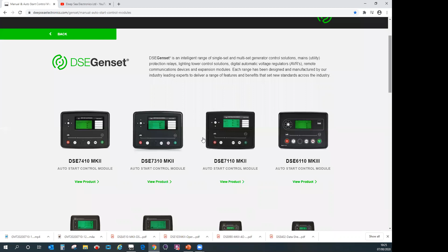So this one here, the auto start control, if we take a common module, which is a good example, the 7310. 7310 means that it's a standalone generator controller, and basically it will start the generator and open and close a breaker. Okay, and it will do that automatically. When it's in auto mode, if someone wires an input to the controller and flicks a switch, the generator will start automatically, or it might be on a schedule, so it will start automatically every couple of days or every couple of hours. Or it may be that manually you want to start it, so you just go and press the manual button and start the generator. And I'll show you how that's done shortly.